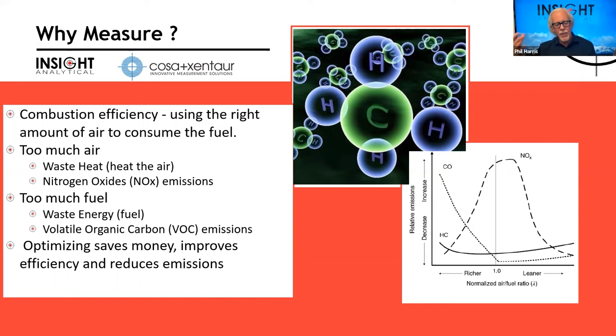From a chemist's perspective, we call it a stoichiometric burn, but we get better efficiencies if we use the right amount of air to consume the fuel. We don't want to use too much and we don't want to use too little. If we put in too much air, we're making that burner heat up a bunch of air, which doesn't necessarily do work for us. If we're using this for a steam generator, we want to use that energy that's in the fuel to generate steam, not to heat up a bunch of excess air.